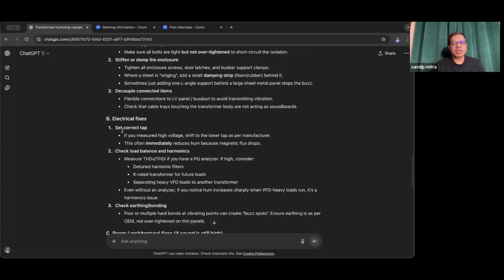Electrical fixes: set the correct tap, and change it if needed. Check, if you measured high voltage, shift to the lower tap as per manufacturer. This often immediately reduces hum because magnetic flux drops. Check load balance and the harmonics. So measure the THDV or THDI. If you have a PQ analyzer and it is high, consider detuned harmonic filters, K-rated transformer for future loads, and separating heavy VFD loads to another transformer. Even without an analyzer, if you notice hum increases sharply when VFD heavy loads run, it's a harmonics issue.